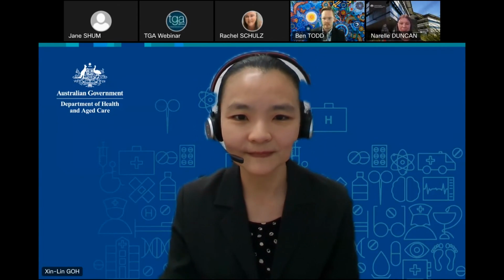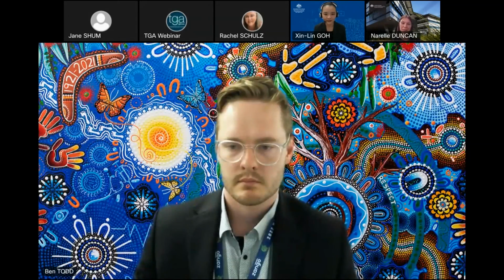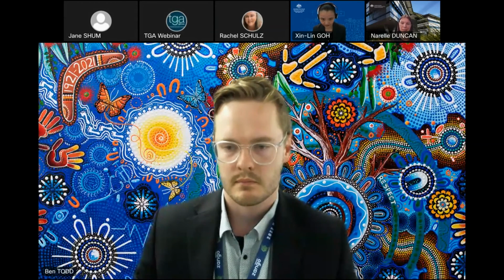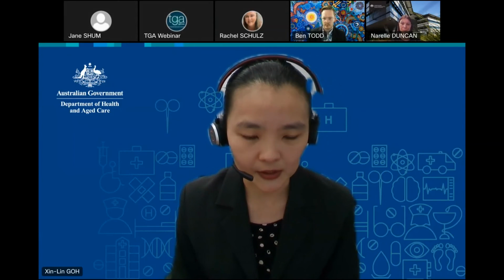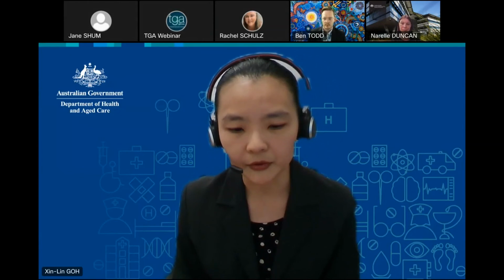Thank you. Our next question is, can an ARTG for the same kind of device be linked with more than one ME? No, so each ARTG entry can only be linked to a single manufacturer evidence. So as mentioned earlier, we encourage all sponsors to associate the ARTG entry with the most relevant ME and to hold evidence of all other ME that's required for the ARTG.